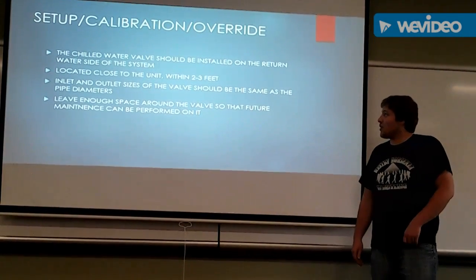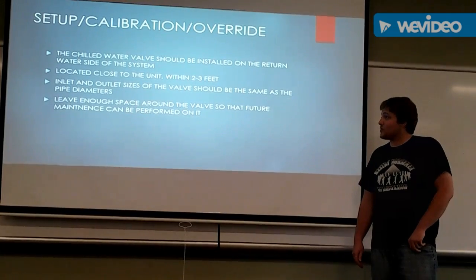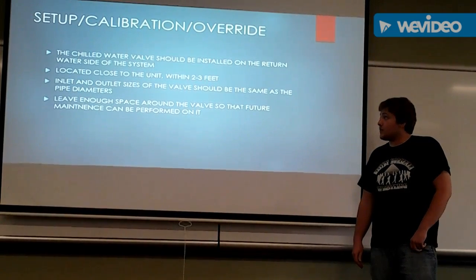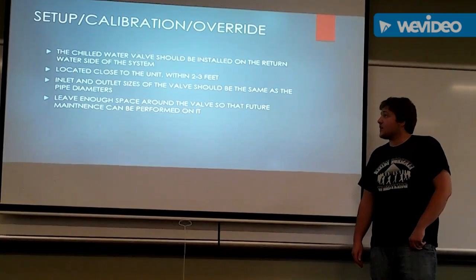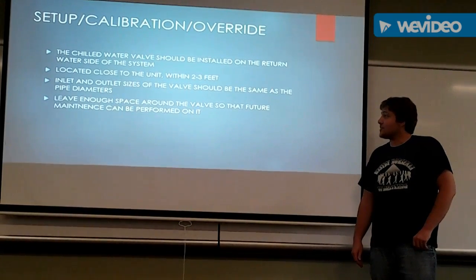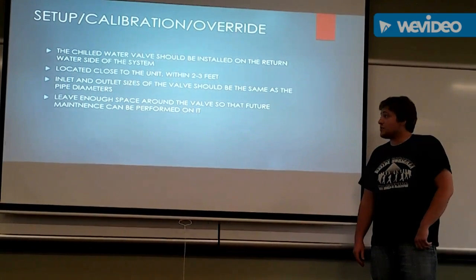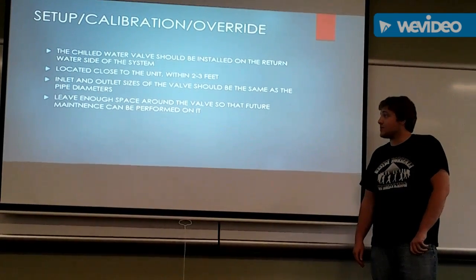The chilled water valve should be installed on the return water side of the system, located close to the unit, within 2 to 3 feet. Inlet and outlet size of the valve should be the same as the pipe diameters. Leave enough space around the valve so that future maintenance can be performed on it.